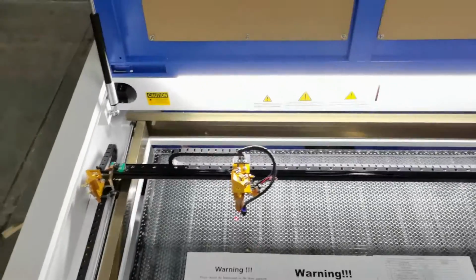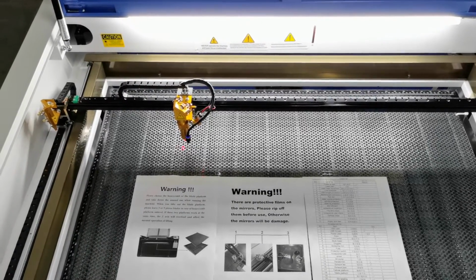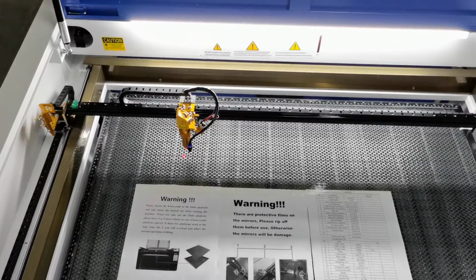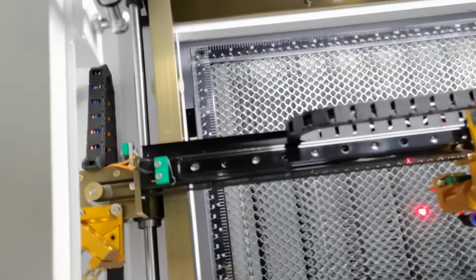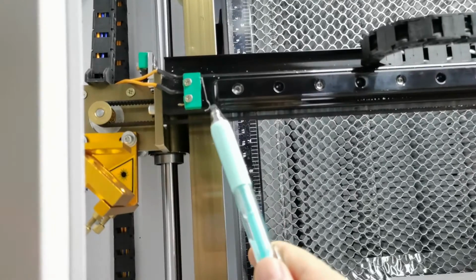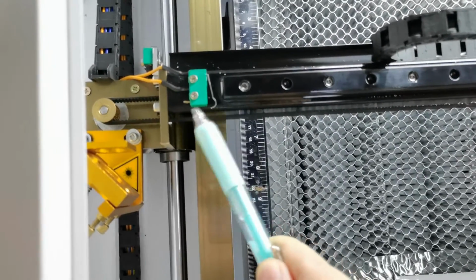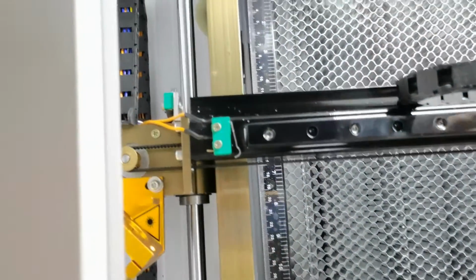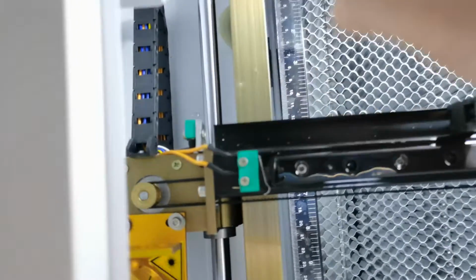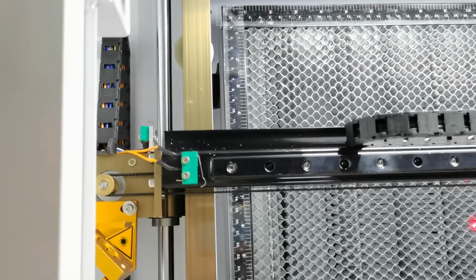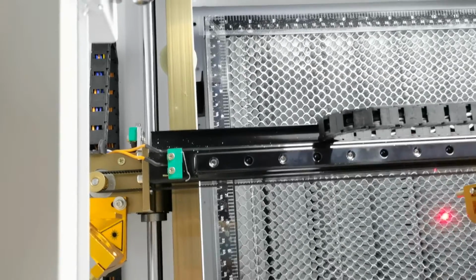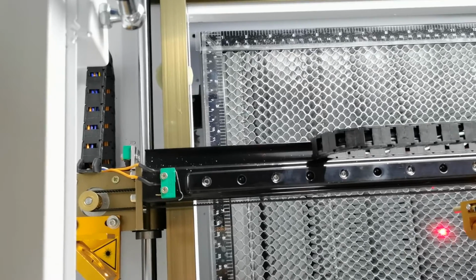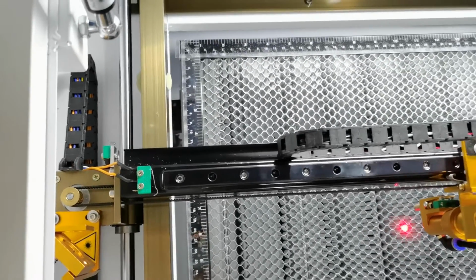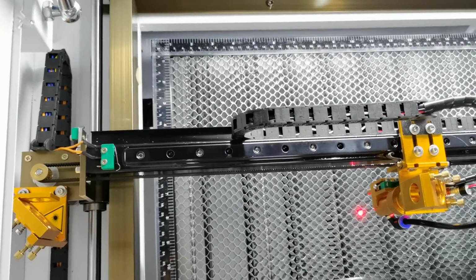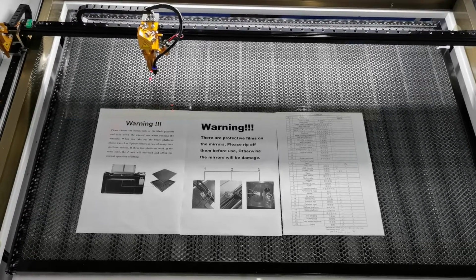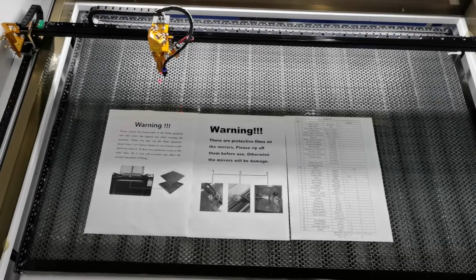Okay. The machine starts. The laser head will go to its home on the left top, and this switch called X homing switch needs to be triggered. Also, the Y homing switch needs to be triggered. That means the laser head finds its origin at the top left. This is the motion origin, and then the laser head will go to the work origin, anywhere you set. Then you will need to move the machine table up and pick the toolbox out.